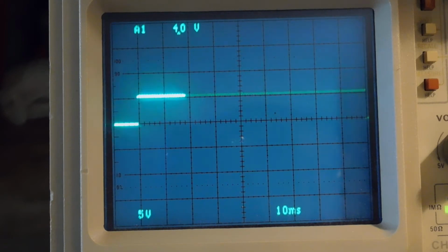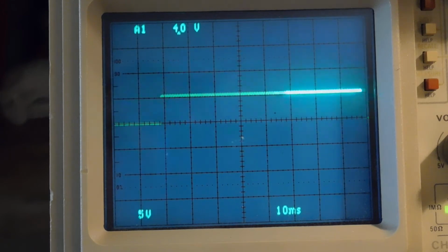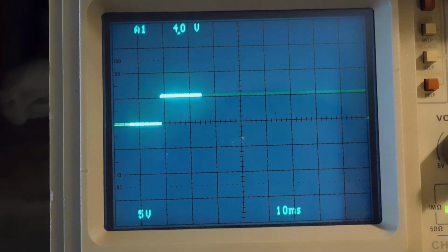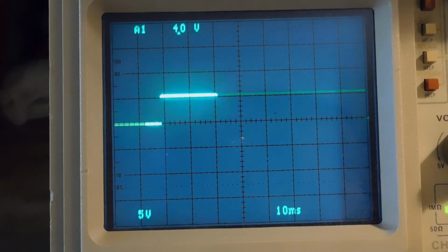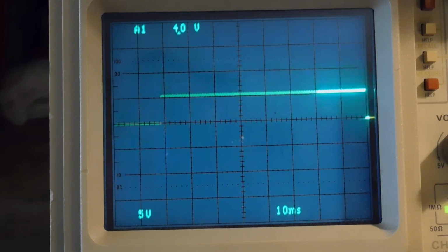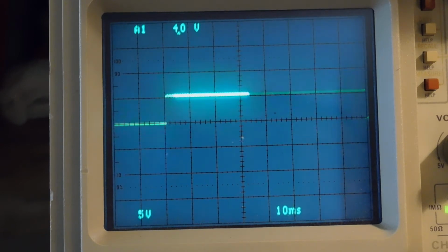So let's set the gain now to 2. So we're going to set the gain to 2, so our pulse width doubles. 2 times the error, which is we're 707 and we're 698 on the actual pressure from the transducer. So that's about 9. So your 2 times 9 is 18. You're at about 18 milliseconds. And you see it jumps a little more because the gain is 2. So 1 torr off and the gain will jump by 2 or 4 depending on that.